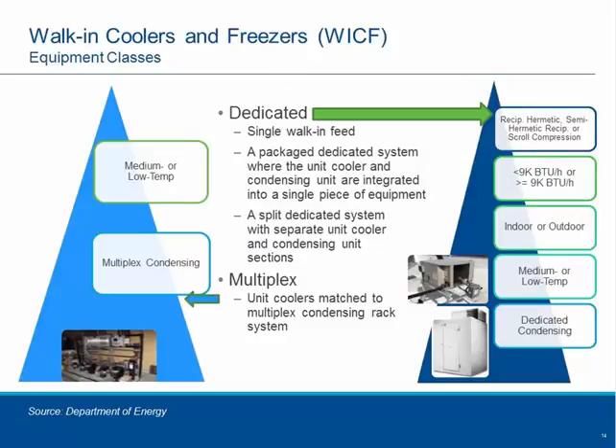Let's move on to walk-in coolers and freezers. Here's how the stack-up looks when it comes to the classes of equipment. On a multiplex system, this is basically almost like a parallel rack system. It's basically a walk-in cooler or freezer, or freezers, that will be connected to a rack system, a multi-compressor rack system, similar to what we see in supermarkets. But a lot of the installed base is in this dedicated condensing unit, where there's an actual specific one-to-one ratio with a condensing unit that is located on the outside of the service area of the walk-in cooler or freezer.